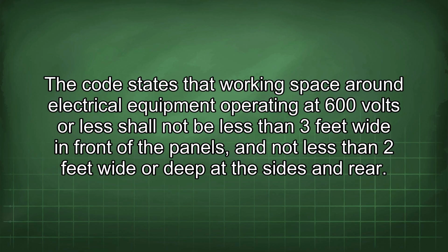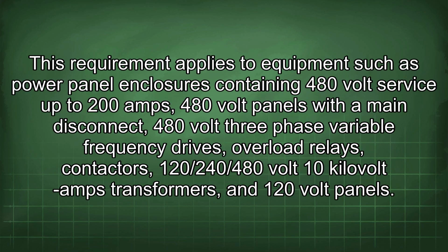than 3 feet wide in front of the panels and not less than 2 feet wide or deep at the sides and rear. This requirement applies to equipment such as power panel enclosures containing 480 volt service up to 200 amps, 480 volt panels with a main disconnect, 480 volt 3-phase variable frequency drives, overload relays, contactors, 120/240/480 volt 10 kVA transformers, and 120 volt panels.